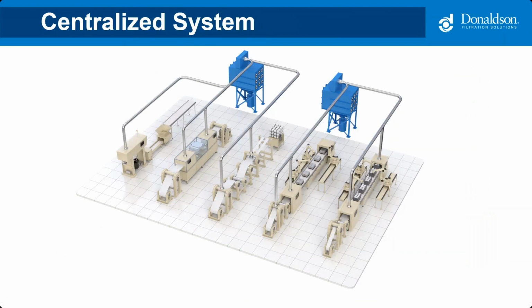Something to really think about as you're designing a new system is the orientation. So what you're looking at here is a hypothetical view of a vent system for a lithium-ion battery facility. The centralized orientation is advantageous as the dust collectors can be in one common area. The benefits of this is it keeps the hazardous dust off of the factory floor so that you maintain electrode integrity. It keeps the dust collectors away from the people working in these areas so that it limits exposure. And it facilitates efficient and focused inspection and maintenance, as well as the dust collectors can be located outdoors in some cases.